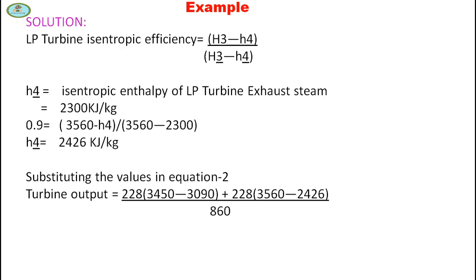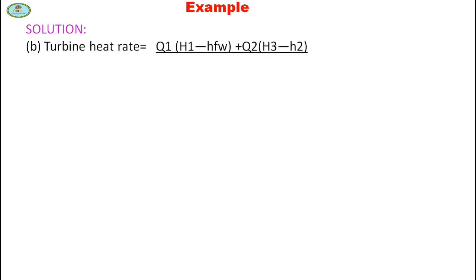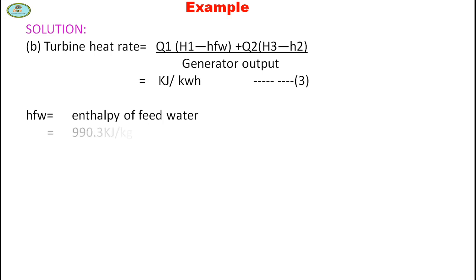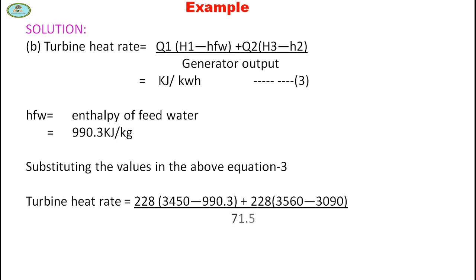Substituting all values, power output equals 75.73 MW, and with generator efficiency of 0.95, the generator output is 71.5 MW. For turbine heat rate: heat rate = [Q1 × (H1 − Hfw) + Q2 × (H3 − H2)] / generator output = [228 × (3450 − 990.3) + 228 × (3560 − 3090)] / 71.5. Turbine heat rate equals 9342 kJ/kWh.